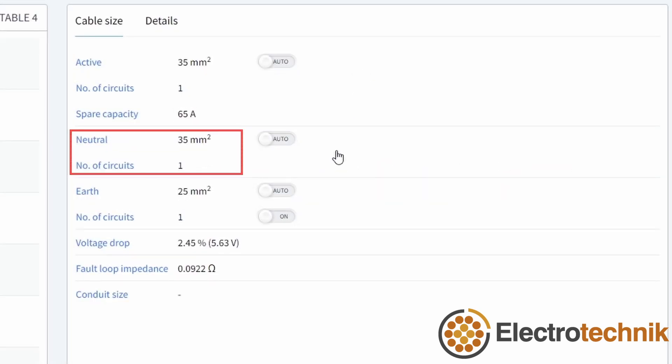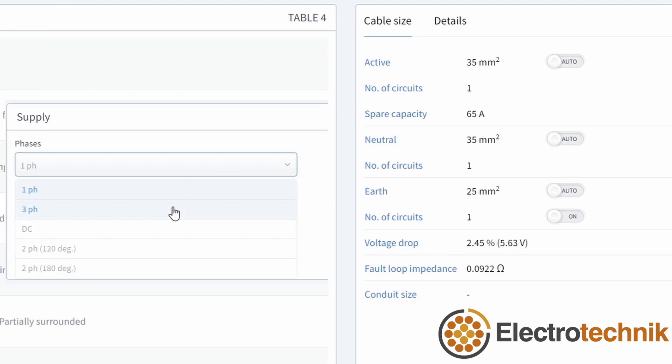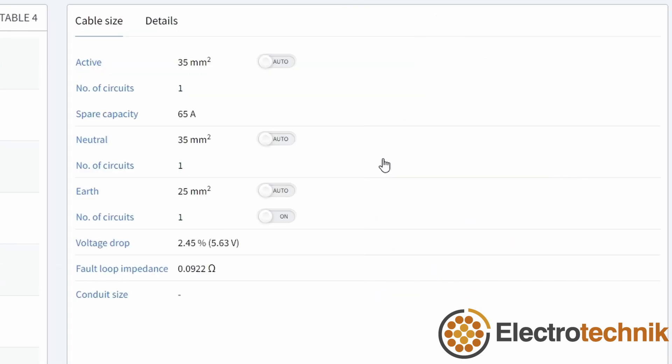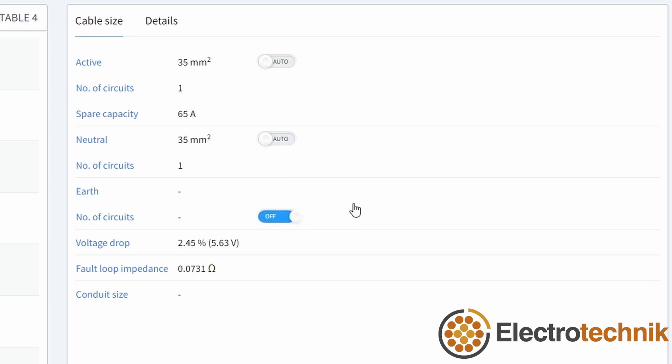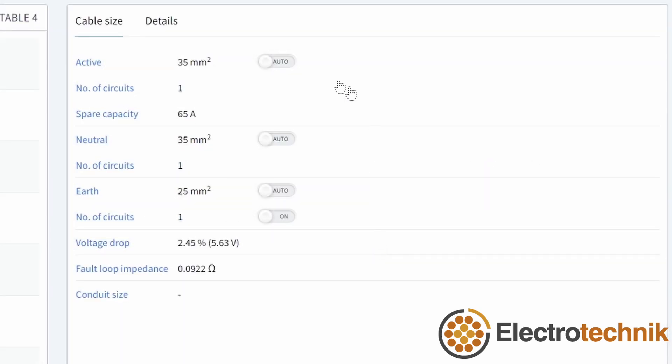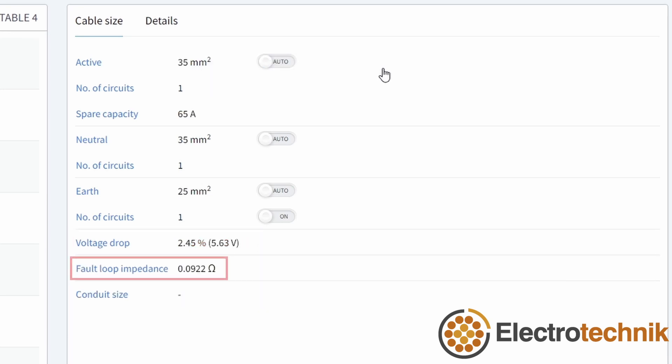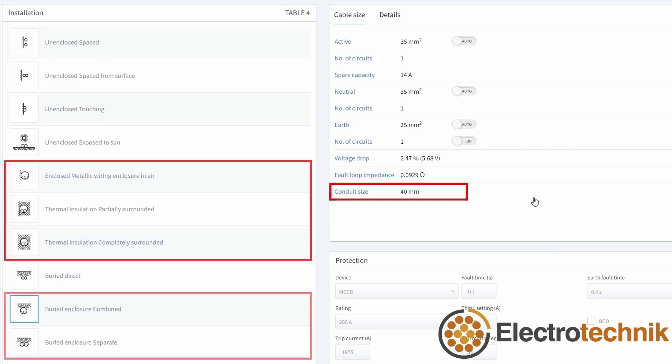Neutral size is automatic or can be manually set for multi-phase circuits. Earth size is automatically calculated based on fault loop impedance and short circuit current. The earth size can be specified and can also be turned off. The actual voltage drop is shown and should be less than the voltage drop limit under the supply section. If it isn't, it will be highlighted in red. The fault loop impedance is also shown and if it is an issue, it will be highlighted in red too. Conduit size is calculated and shown for any installation methods which are in conduits.